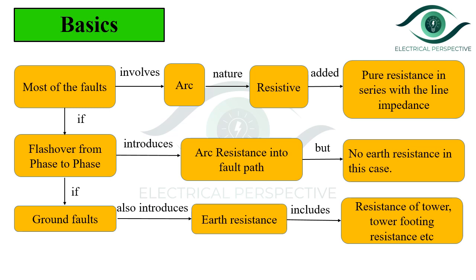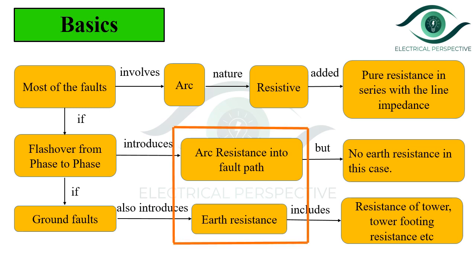The earth resistance and the arc resistance combined together are known as fault resistance. One point should be noted: in case of a phase-to-phase fault, the fault resistance consists of only the arc resistance and there is no earth resistance. But in case of a ground fault, it consists of both arc resistance and earth resistance.